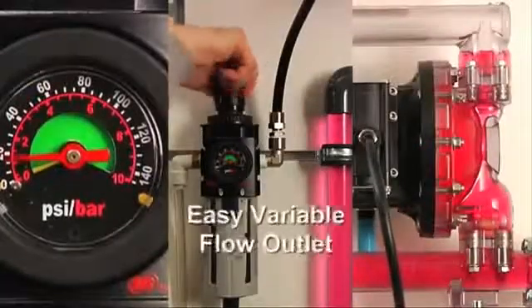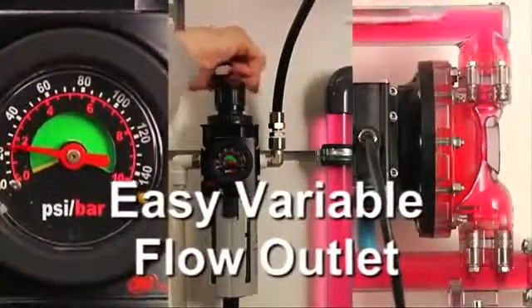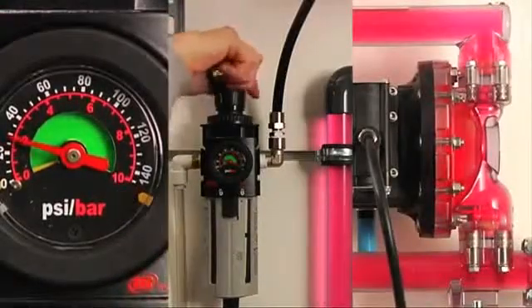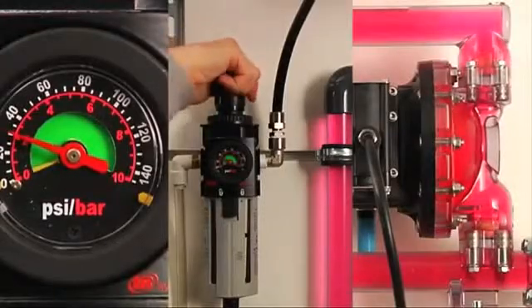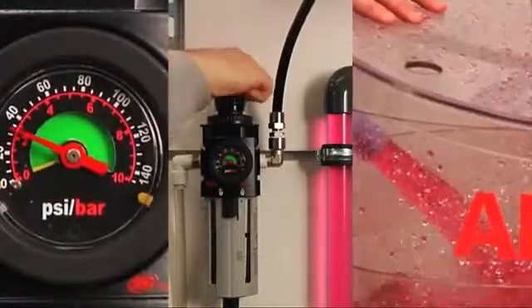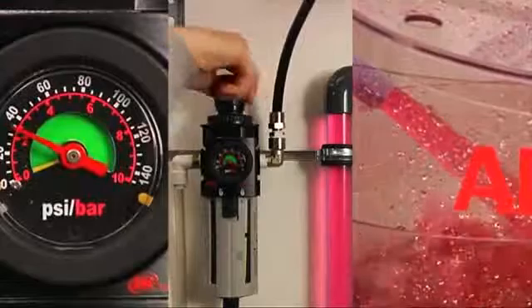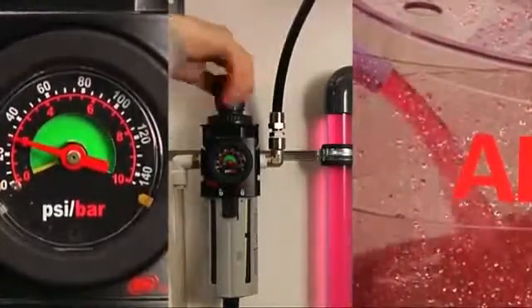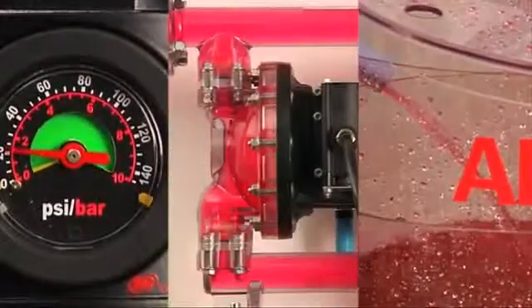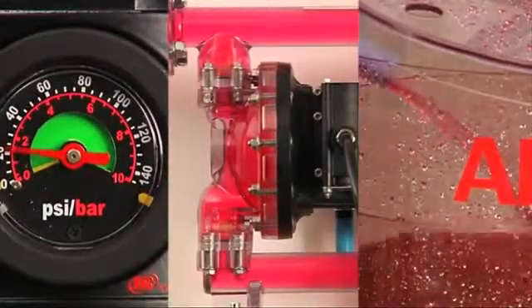Another major advantage of an air operated diaphragm pump is the ability to vary flow and discharge pressure up to 7 bars. This can be executed by just adjusting the air inlet pressure thanks to a simple air regulator placed at the air inlet of the pump. This simple control eliminates the need for expensive motor drives and critical sizing calculations.